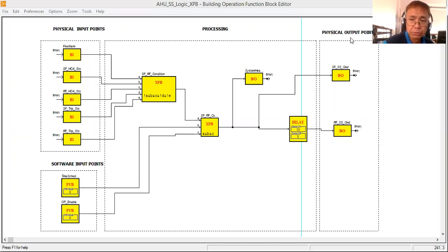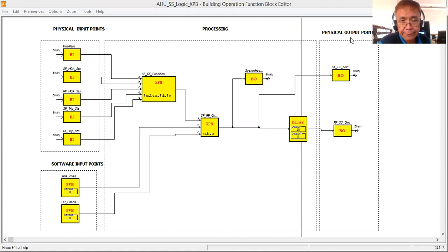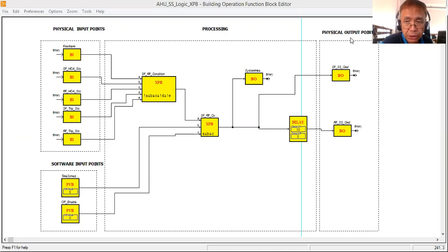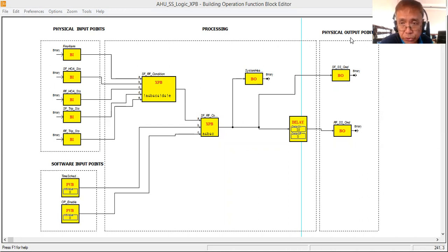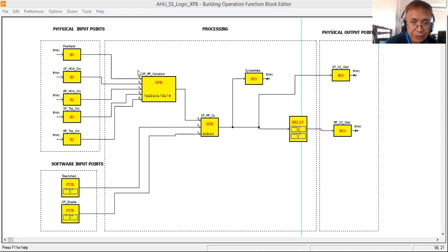Today I'm going to try another approach to programming the supply fan and return fan control logic of our return or recirculating air handling unit. In my previous tutorial I used a combination of different logic gates — an AND gate combined with a NOT gate. Here in this approach, I'm using an expression block.